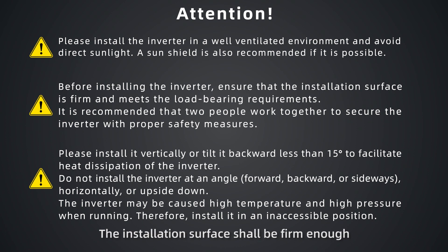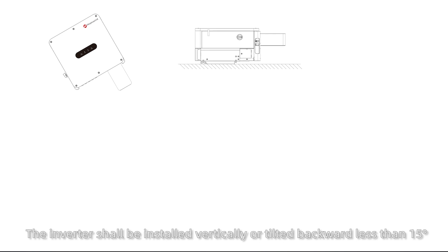The installation surface shall be firm enough and meet the load-bearing requirements. The inverter shall be installed vertically, or tilted backward less than 15 degrees.